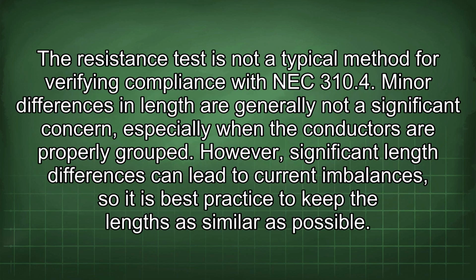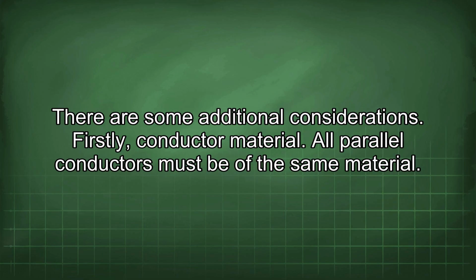The resistance test is not a typical method for verifying compliance with NEC 310.4. Minor differences in length are generally not a significant concern, especially when the conductors are properly grouped. However, significant length differences can lead to current imbalances, so it is best practice to keep the lengths as similar as possible. There are some additional considerations.